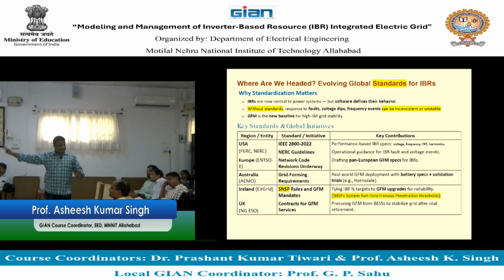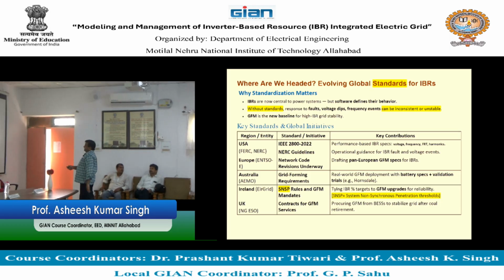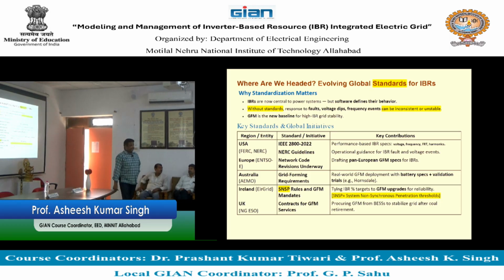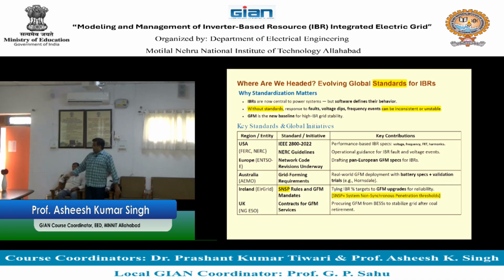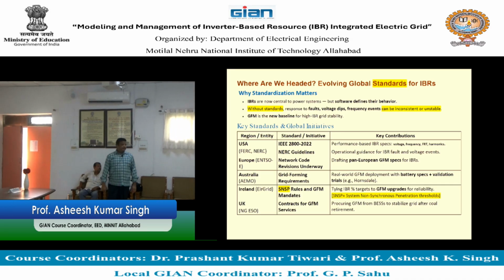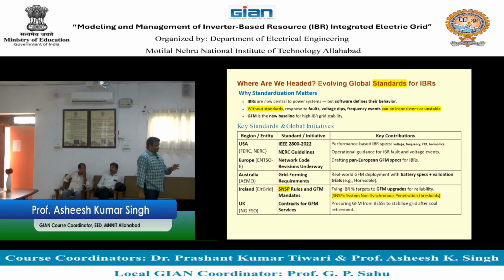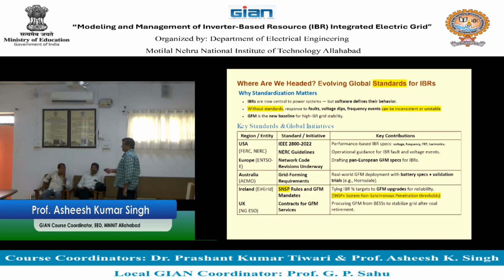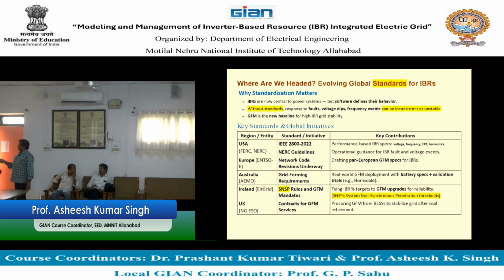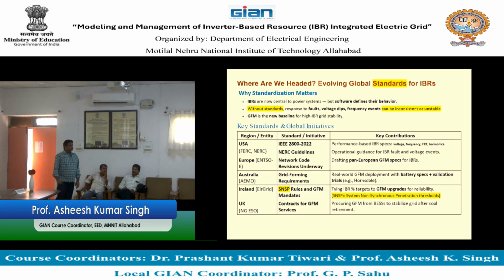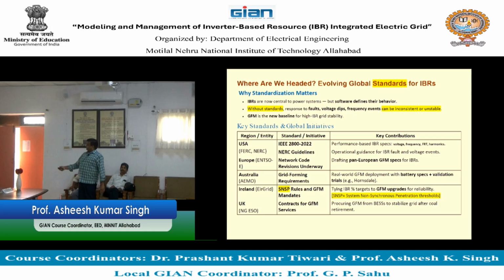So the key standards and global initiatives are: in USA there are different bodies, FERC, NERC. And this IEEE 2800 standard is also there, which was released in 2022. This IEEE 2800 contributes performance based IBR specifications for voltage, frequency, FRT and harmonics. And these NERC guidelines are operational guidance for IBR fault and voltage events only, so they are not the complete one.